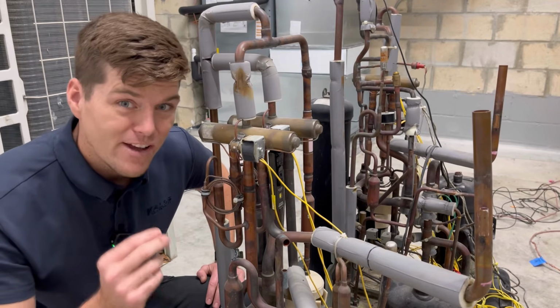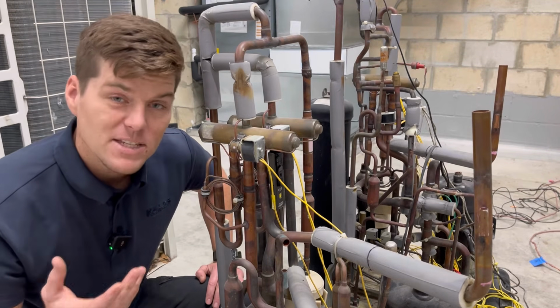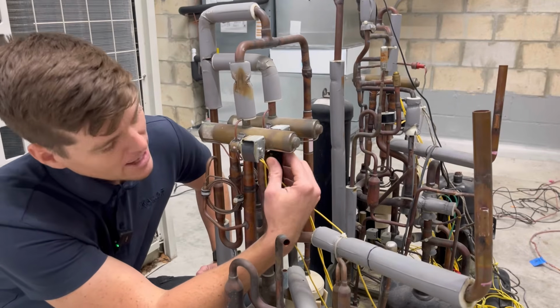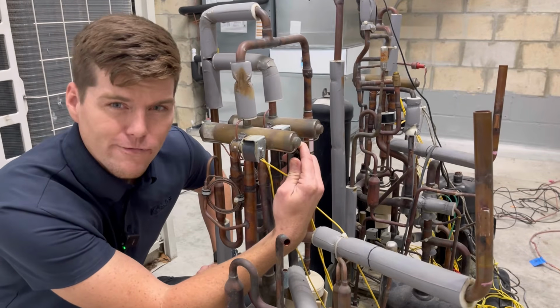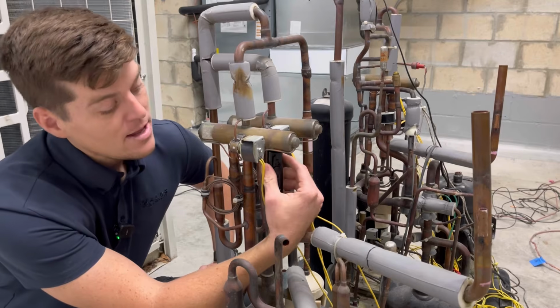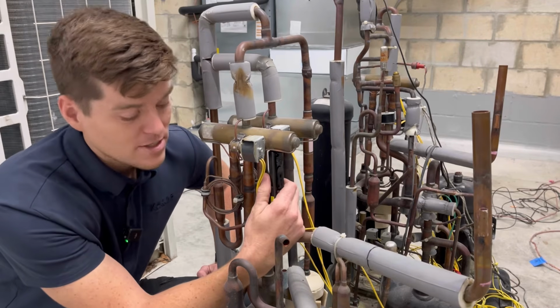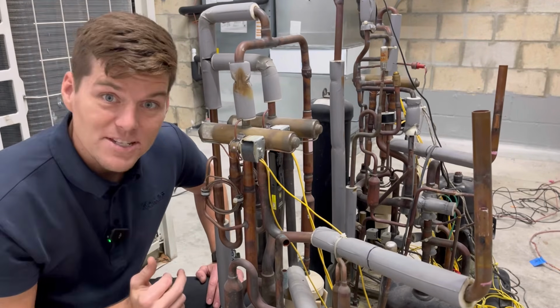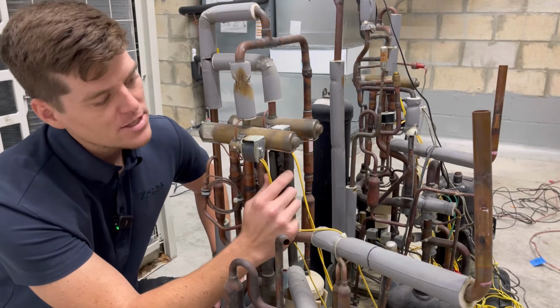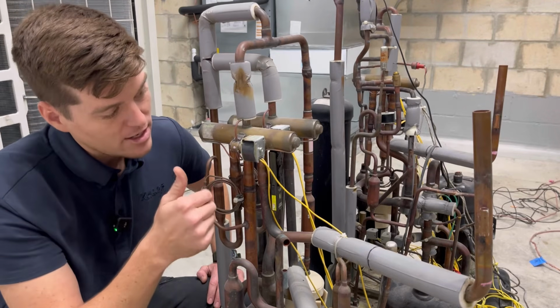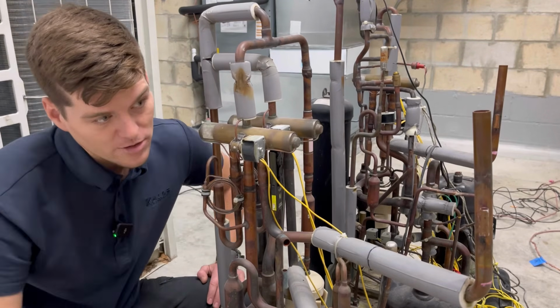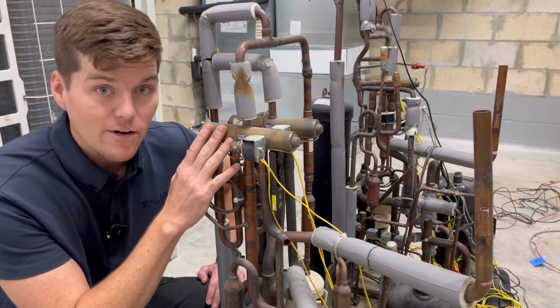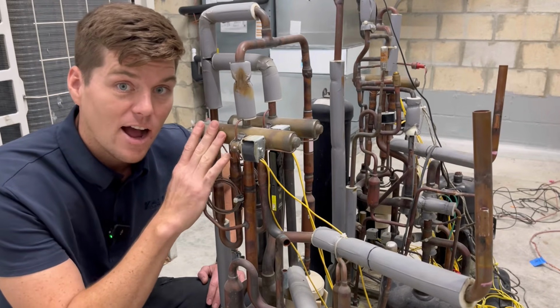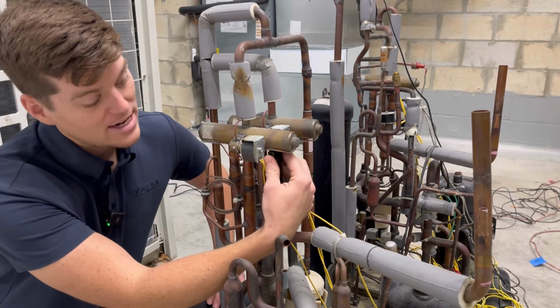But if I wanted to just verify, or maybe I wanted to see it shift, maybe it's getting stuck halfway in between. Maybe this magnet is energized right here in the middle and not on the far end or on the far left. That would be a partial shift, right? And you would see where you're actually bleeding hot gas to both sides of the chamber. But for this sake here, we can see that our suction line is connected, our hot gas line is going to the outdoor heat exchanger. This four-way valve is in a cooling state, right? It's sending hot gas to the outdoor heat exchanger, and it is not stuck.